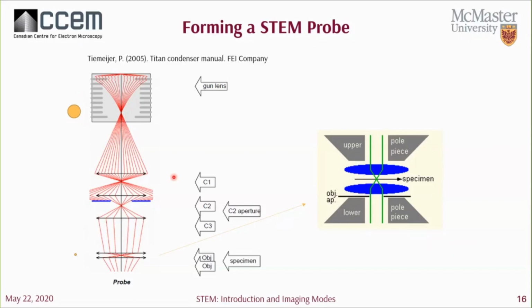In the Titan, we have a 3 condenser lens system. The probe is also formed using a C2 aperture, and that helps define the convergence angle of your beam. And we have here a set of twin objective lenses, in which the upper pole piece is strengthened to converge our beam into a point on our sample.